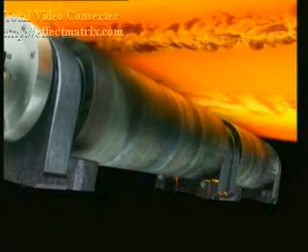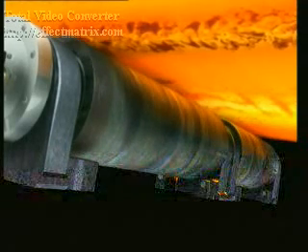A slanted roller does not necessarily affect the quality of the slab, but it does generate an axial force in the roller, which may lead to bearing overload. If a roller is blocked, for example because of a bearing failure, the slab may become excessively scratched. This lack of quality either leads to production losses or machining of the damaged slab. In the worst case, a blocked roller might even cause a breakout.